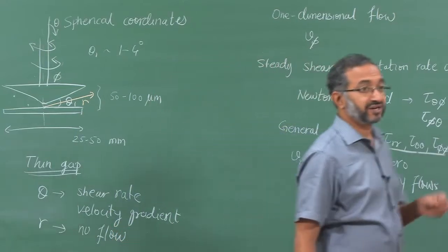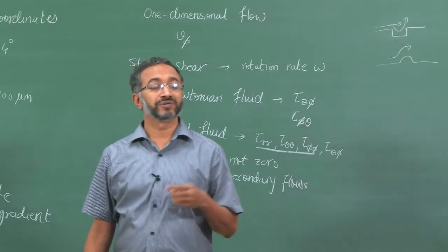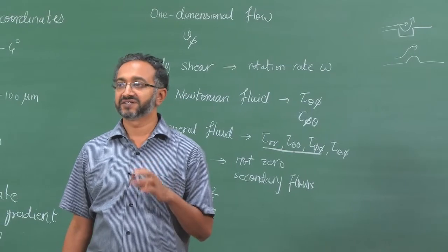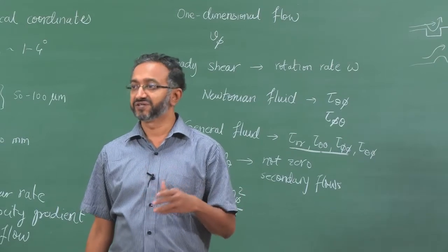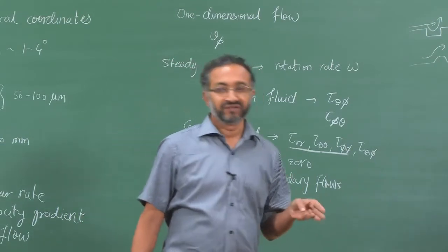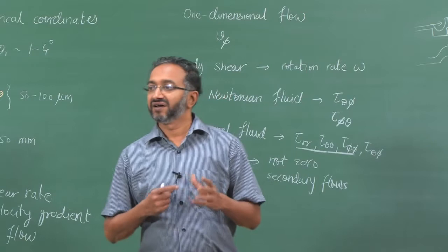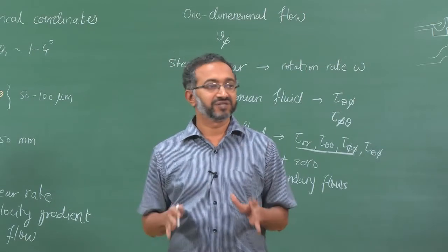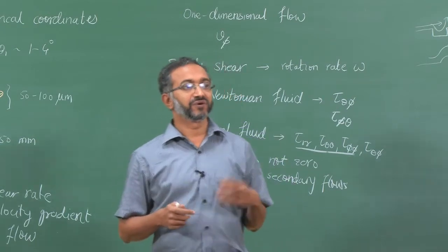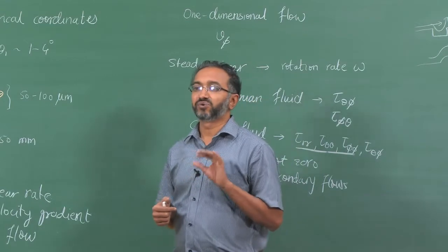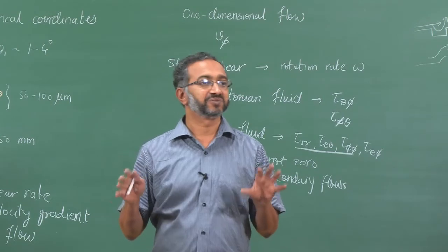So, this depends on the construction of the instrument and its stability, and of course the stability of the instrument may also be different depending on what conditions it is being operated upon. For example, if we take the instrument to very high torques, which are limits of the instrument, or we take the motor to very high rotation rates, we might expect that some of the non-rigidities associated with the overall instrument might come into play, and we may get a small misalignment. Therefore, some of these features are more often than not experienced when we are operating the instrument at extremes in terms of the instrument capabilities.